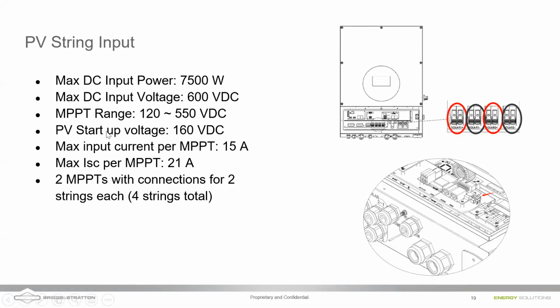MPPT range 120 to 550, and the startup voltage is 160. So the max input current per MPPT is 15 amps, and do not exceed the max short circuit current of 21 amps. That's normally about 2 panels, maybe 3 panels in parallel, depending on the short circuit current of your panel. So be careful not to exceed that short circuit current.